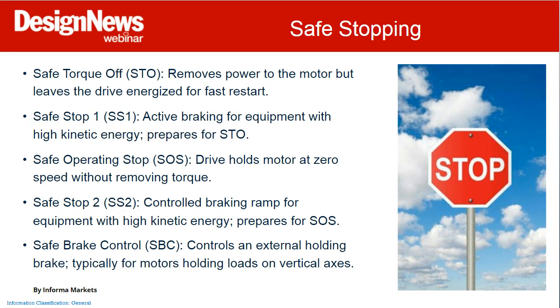So the key thing that basically everybody knows about is safe torque off. You can remove torque to the motor, but you leave the drive energized so you can restart quickly. There's a variant on that, safe operating stop, which doesn't even remove torque from the motor, it just holds the axis at zero speed. Neither one of these things actually stops the axis.